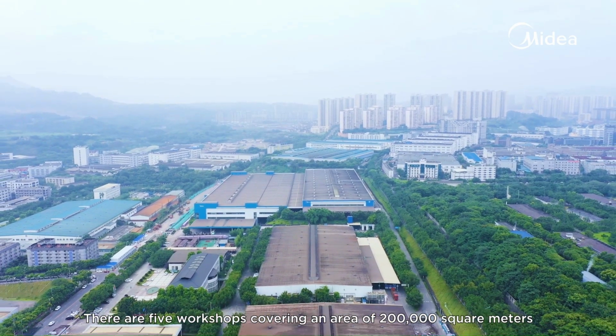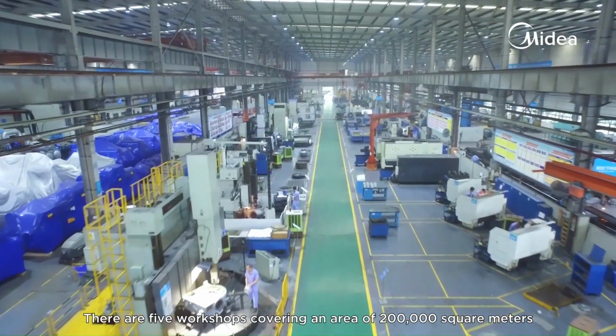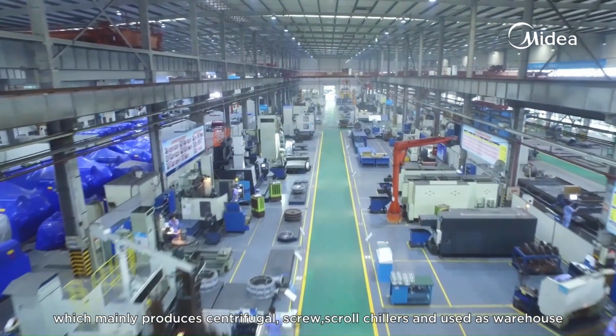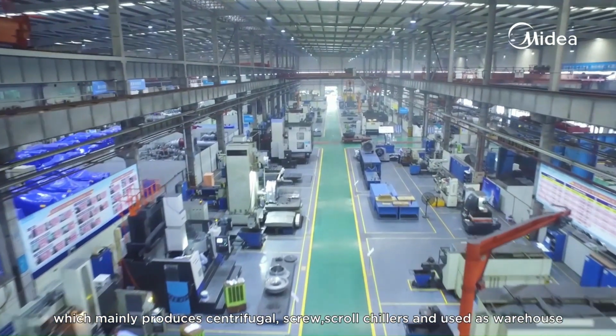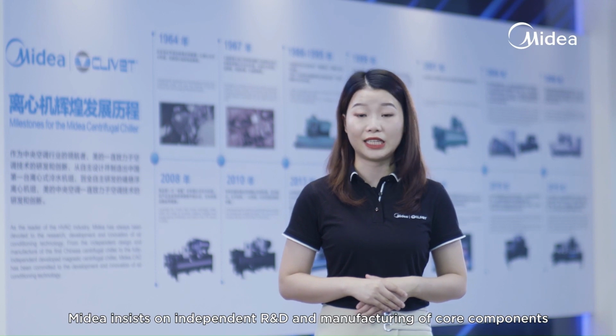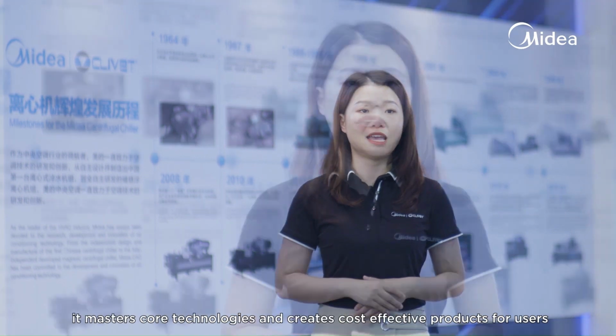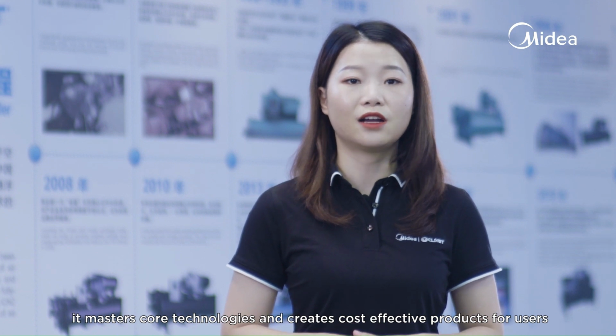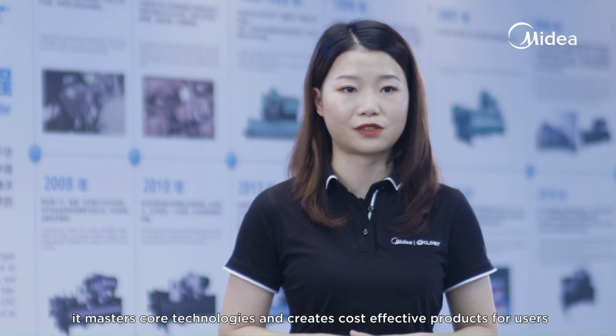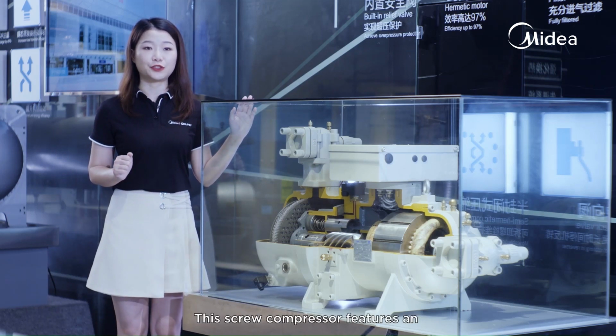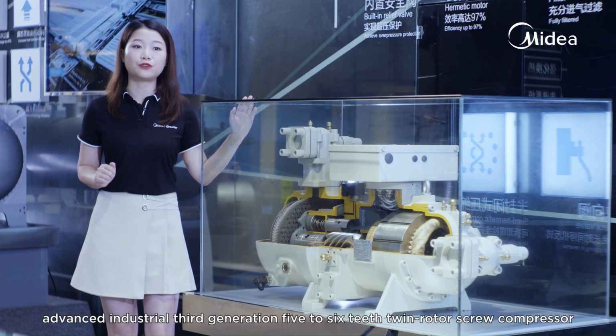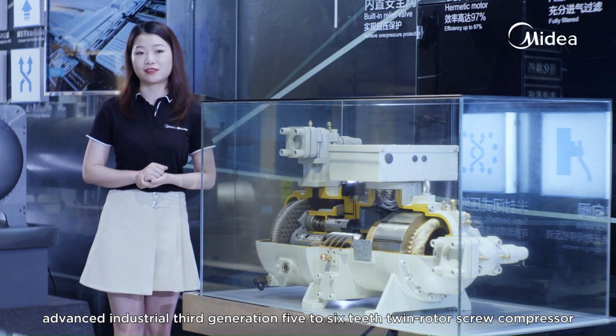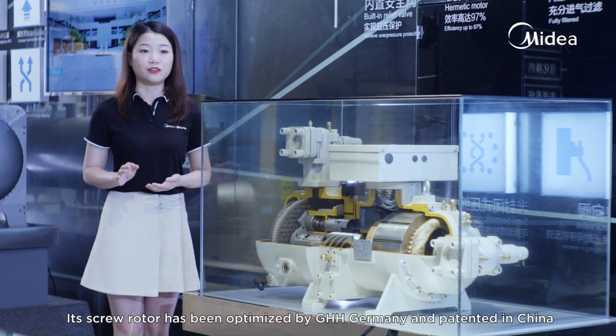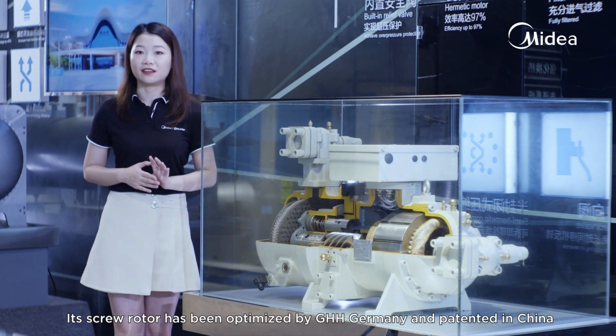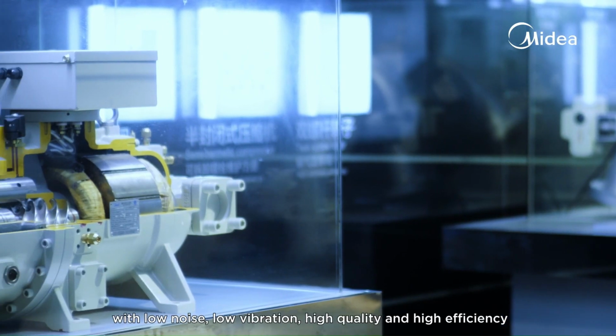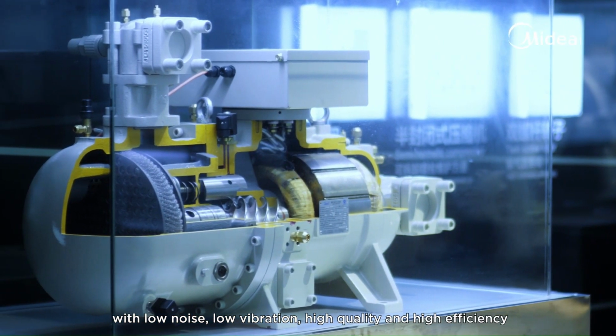There are 5 workshops covering an area of 200,000 square meters, which mainly produces centrifugal, screw chillers and used as warehouse. MIDEA insists on independent R&D and manufacturing of core components. It masters core technologies and creates cost-effective products for users. This screw compressor features an advanced industrial 3rd generation 526T twin-rotor screw compressor. Its screw rotor has been optimized by GHH Germany and patented in China, Europe, USA, and Japan. With low noise, low vibration, high quality, and high efficiency.